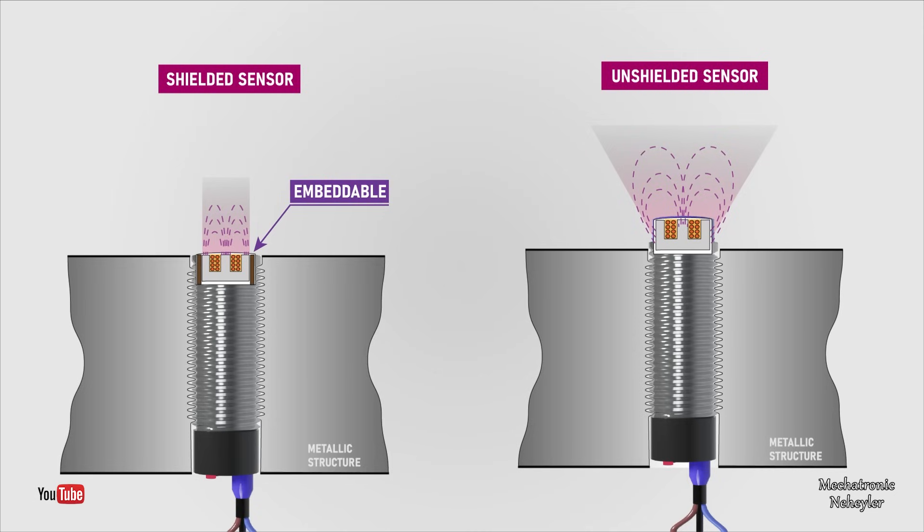An unshielded sensor has a protruding face, and inside, the coil does not have a metal shield around it, giving it a much larger sensing area. If the sensor is not shielded, its installation necessarily has to be non-flush — the active face of the sensor protrudes out and its operation is not affected by the metal structure that supports it.